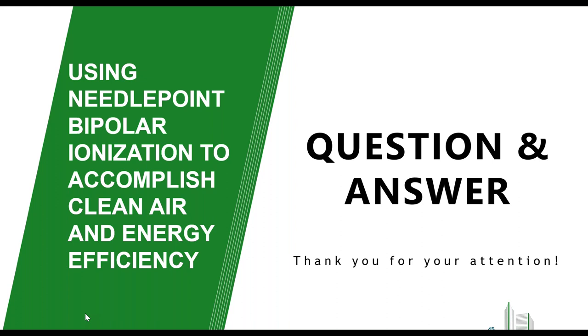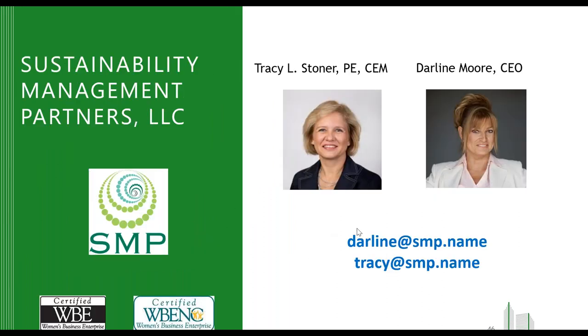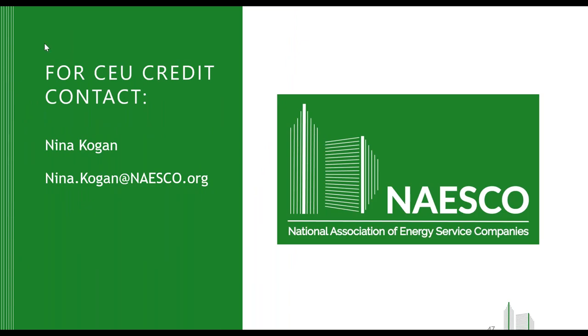UV, you know, we do compete with UV and HEPA filters. That's a very true statement. What UV does, it does well. But what the needlepoint bipolar ionization technology does, it does better. The reason I say that is because we travel with the airstream and air touches everything, so you can impact whatever the air is touching. With UV, the light has to see whatever it is attacking. So whatever virus, pathogen or bacteria, it has to actually be in the light before it can impact it. So the technology that travels through the airstream is much more effective than just sitting on a coil or sitting in a room stagnant. It is traveling into the spaces and starting the process of creating the positive and negative ions and attaching to the bad stuff.